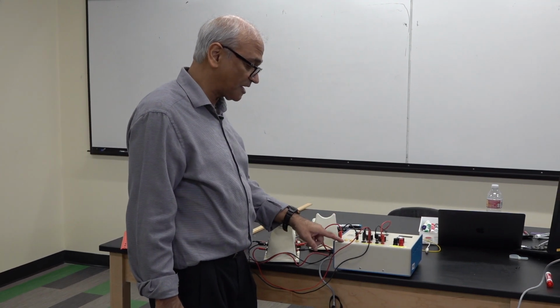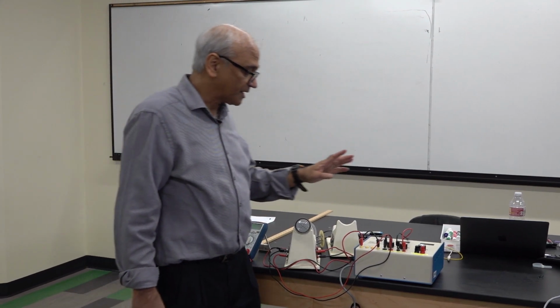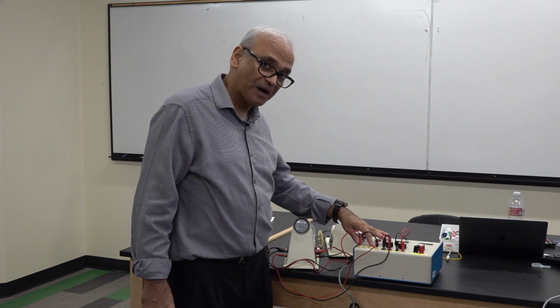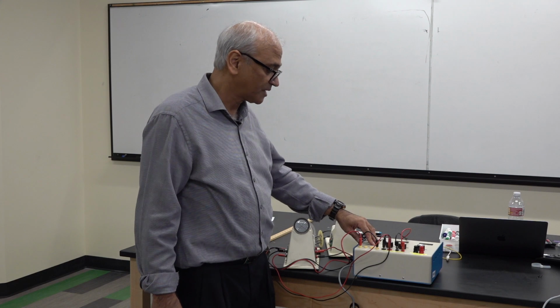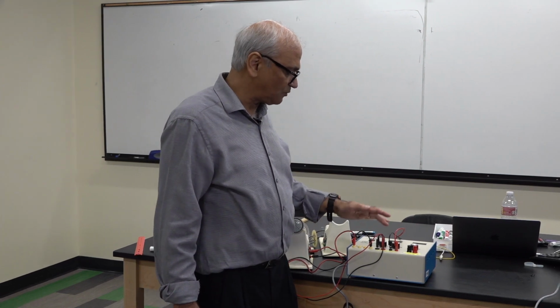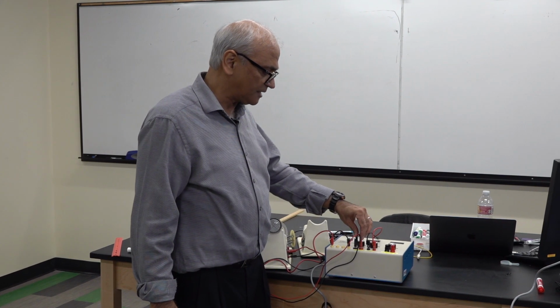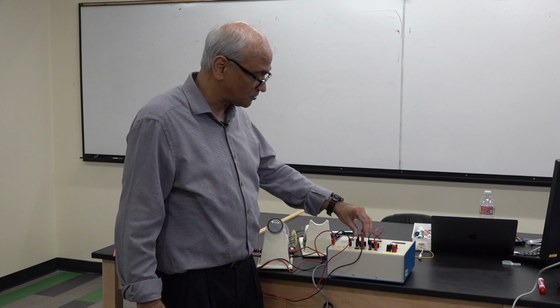There is a little bit of AC over here. You have 3 voltages that we're going to use. This is called the filament bias supply, filament supply. This turns out to be AC right here, and it's about 4, 5, 6 volts. And then we have this accelerating voltage, which will go up to 500, 600 volts over here.